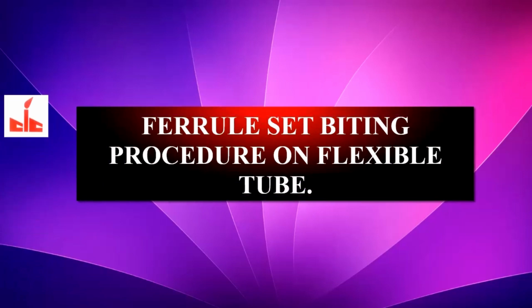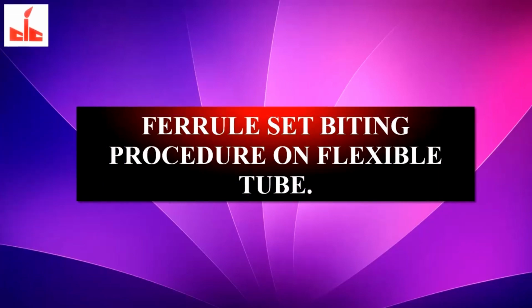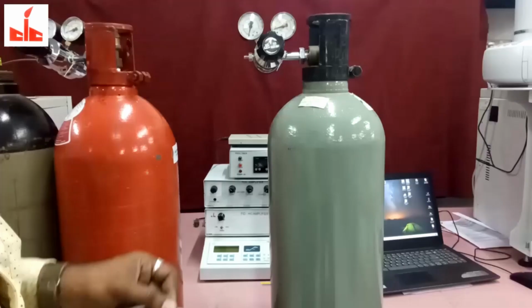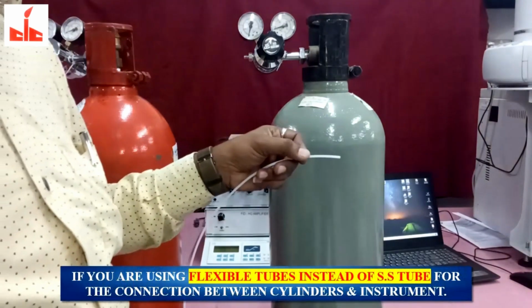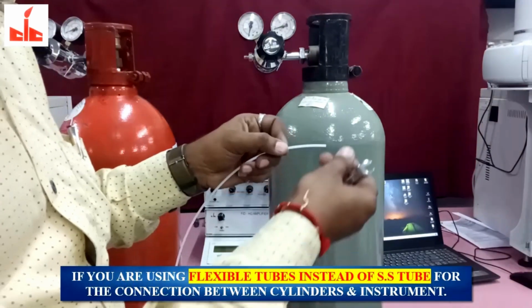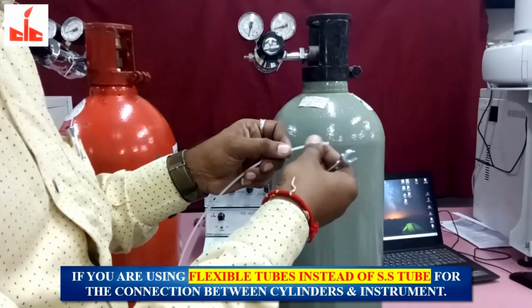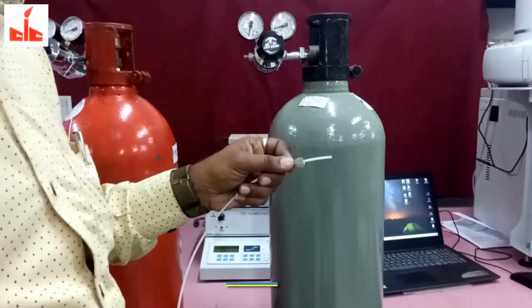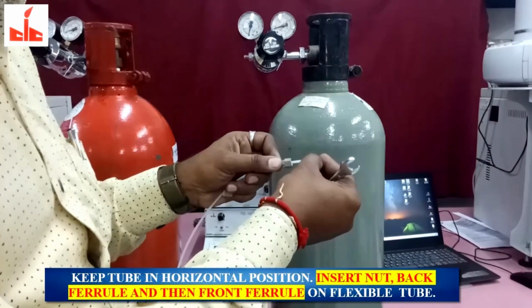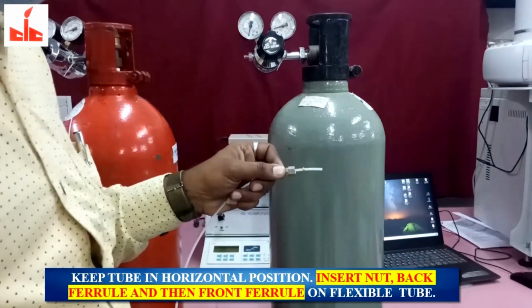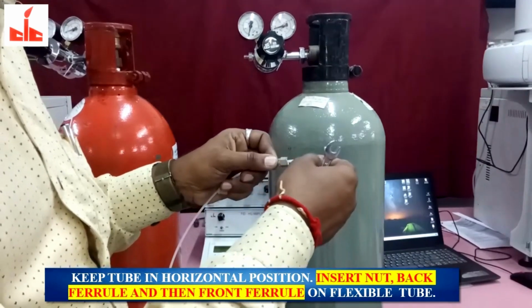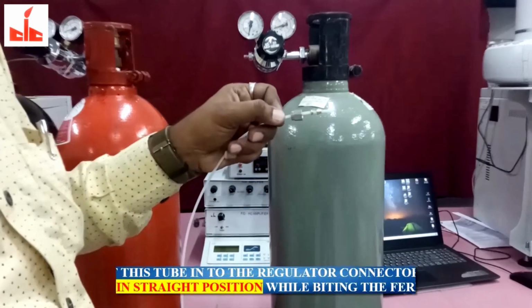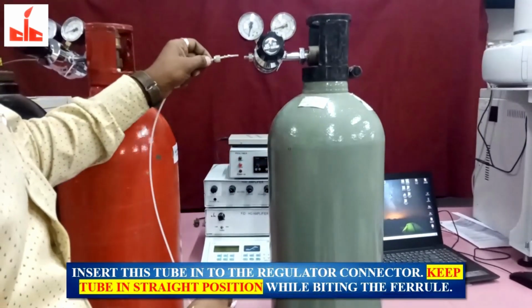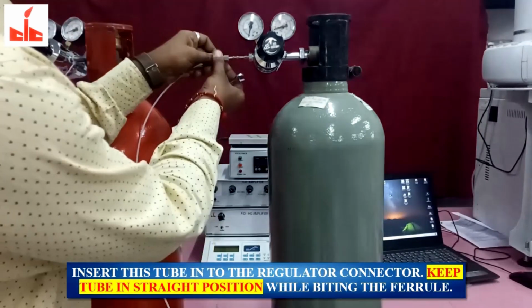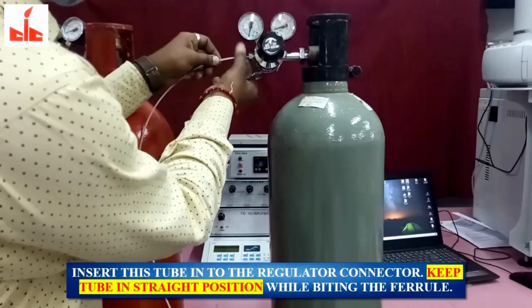Ferrule set biting procedure on flexible tube. If you are using flexible tube, instead of stainless steel tube, for the connection between cylinders and instrument, keep tube in horizontal position, then insert nut, back ferrule and front ferrule on flexible tube. Insert this tube into the regulator connector. Keep tube in straight position while biting the ferrule.